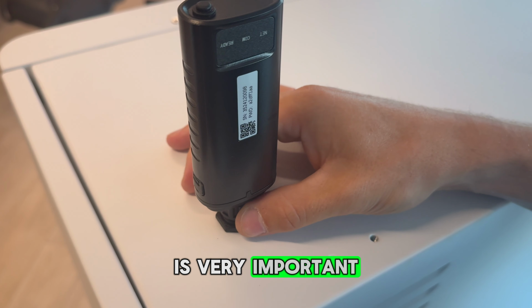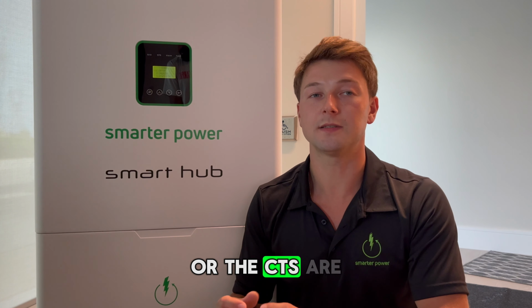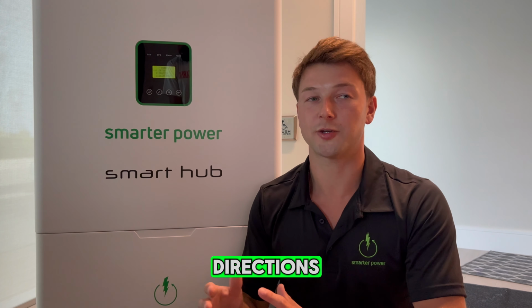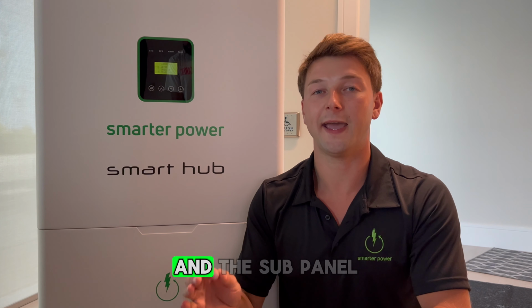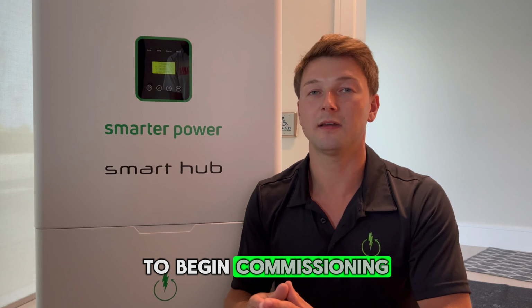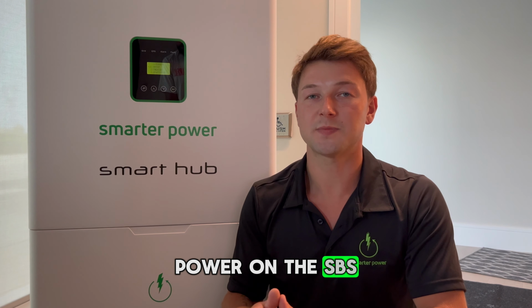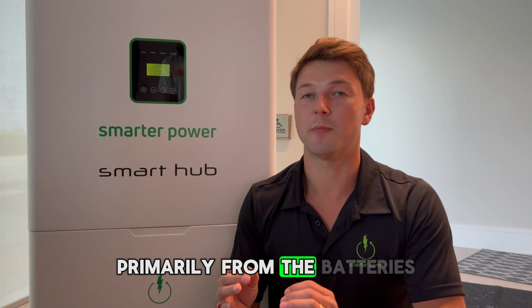It is very important that we ensure that the current transformers, or the CTs, are installed in the correct directions. Refer to the CT section in the Smart Hub user manual. It's very important as well that we turn off all connections to the main service panel and the sub panel. To begin commissioning, power on the SBS primarily from the battery's smart energy source.